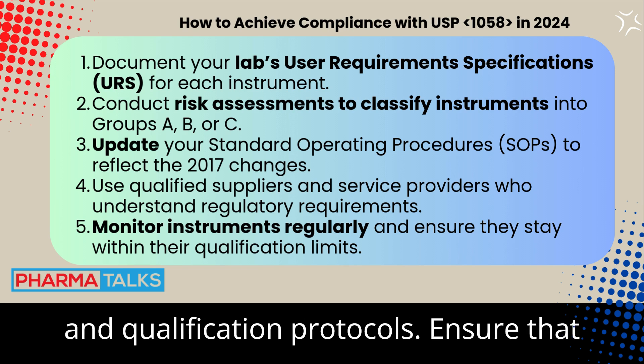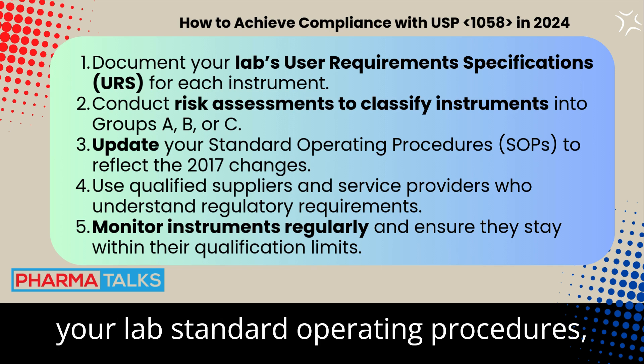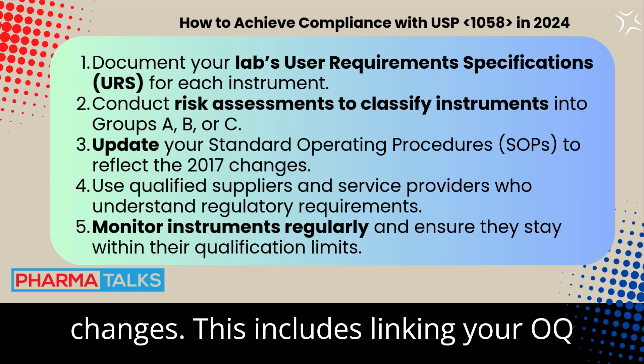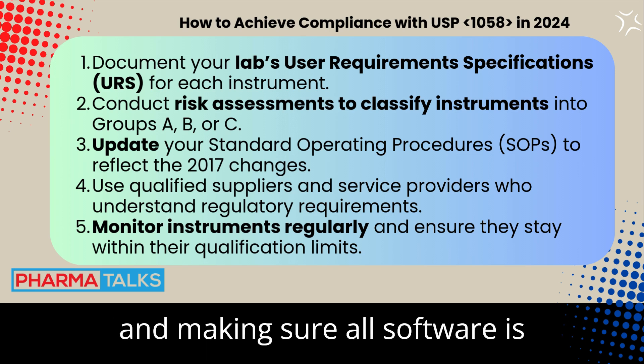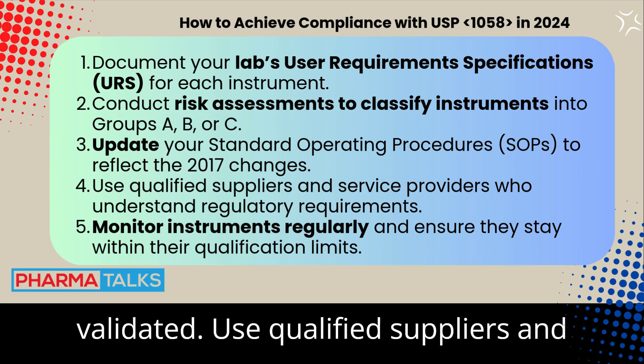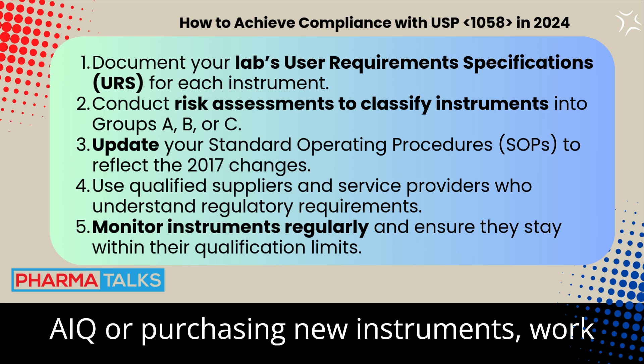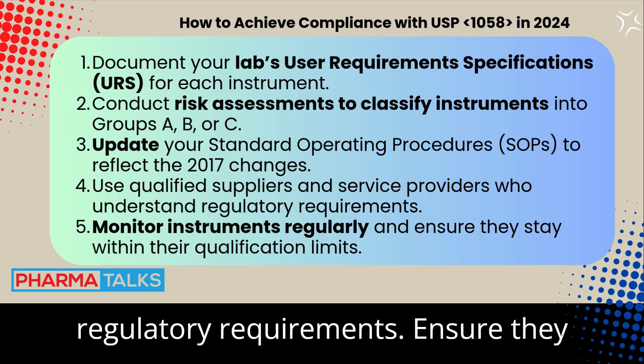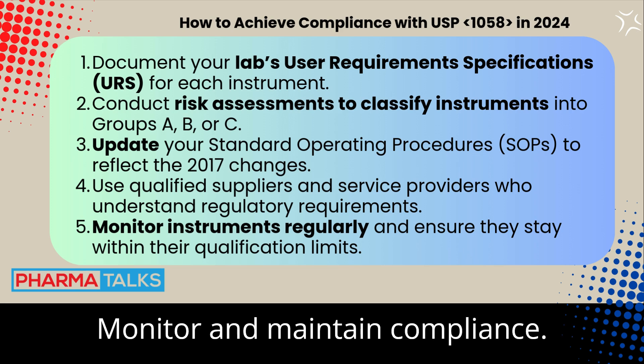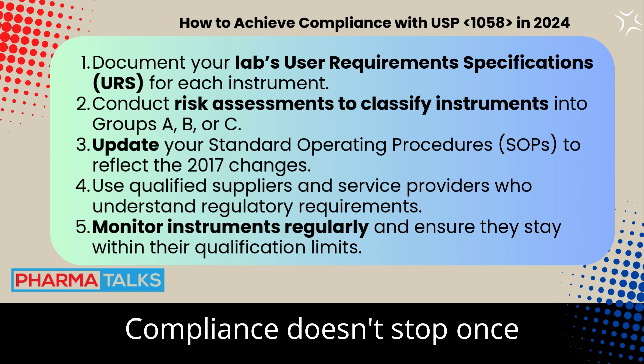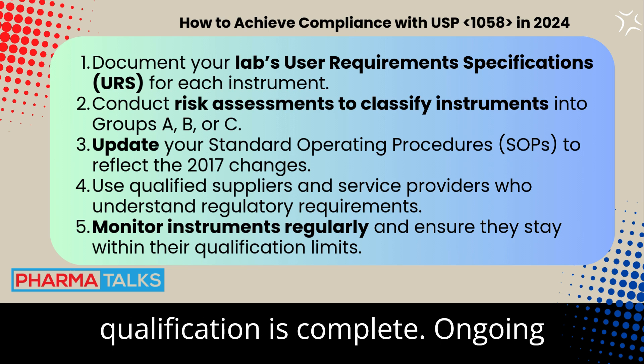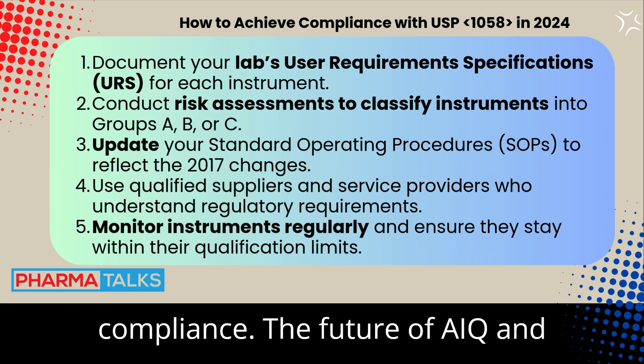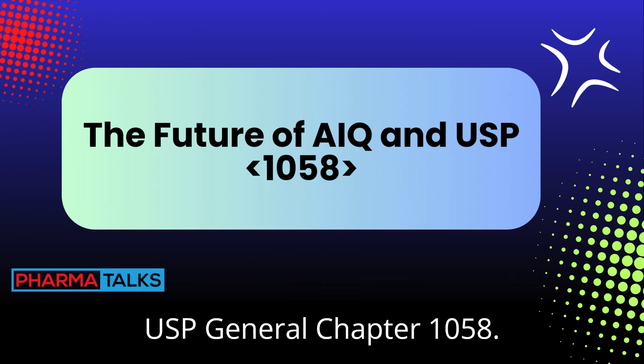Third, update SOPs and qualification protocols to reflect the 2017 changes, including linking your OQ and PQ directly to user requirements and ensuring all software is validated. Fourth, use qualified suppliers and service providers — when outsourcing AIQ or purchasing new instruments, work with vendors who understand the regulatory requirements and provide clear documentation and support. Fifth, monitor and maintain compliance: ongoing performance checks, change control processes, and regular audits are essential to ensuring continuous compliance.